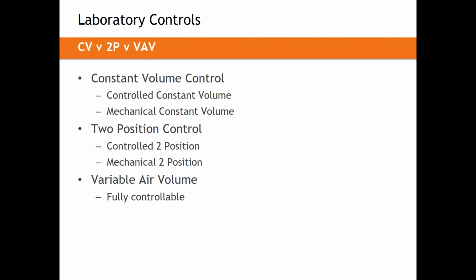It's a fairly similar conversation. For a VAV box or high accuracy terminal, you can achieve two-position control. You can control to a minimum flow and a maximum flow. However, that's still a full VAV box that's just controlled to two different set points. So the equipment required and the capital cost is identical.